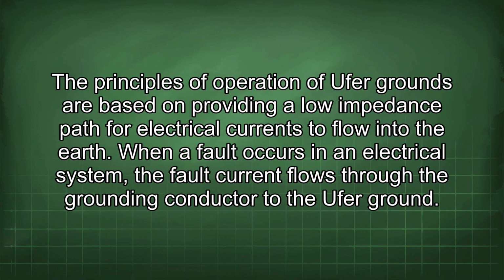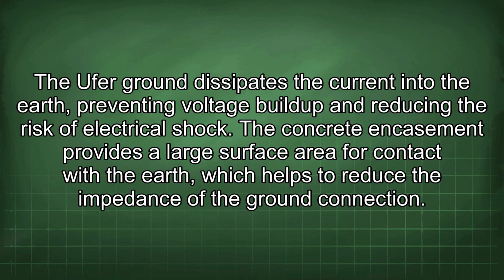The principles of operation of Ufer grounds are based on providing a low impedance path for electrical currents to flow into the earth. When a fault occurs in an electrical system, the fault current flows through the grounding conductor to the Ufer ground. The Ufer ground dissipates the current into the earth, preventing voltage buildup and reducing the risk of electrical shock.